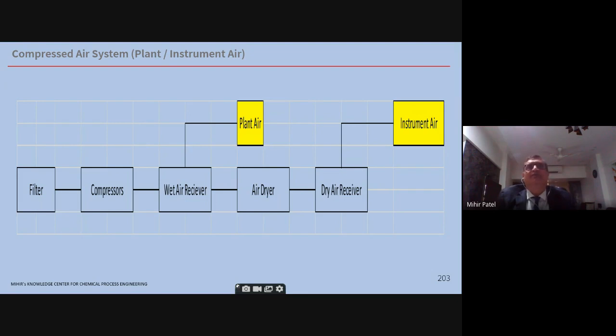The requirement is that plant air can be saturated with moisture, that is okay. Instrument air has to be dry. The atmospheric dew point is normally minus 40 degrees centigrade, and corrosion is not tolerated. Particles are not tolerated because the actuators may get choked and the control valve may not work properly. So the first is the filter. The filter depends on the type of country you are in. Let's say in Saudi Arabia, if you are putting up a project, it's a desert country, you will normally have a dust filter for desert application. So the filters are robust. You have to specify this in the process data sheet.